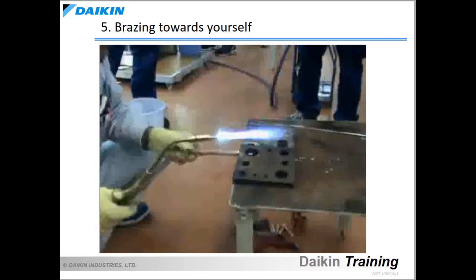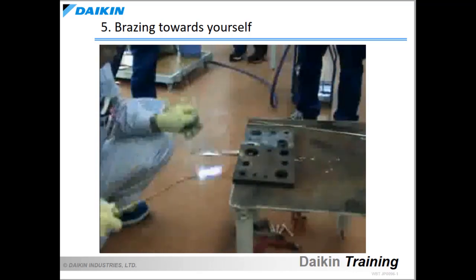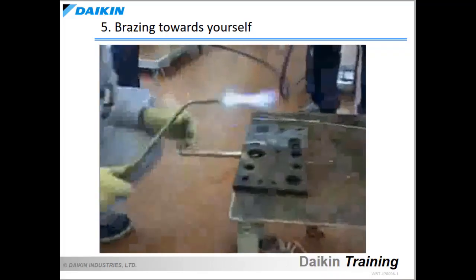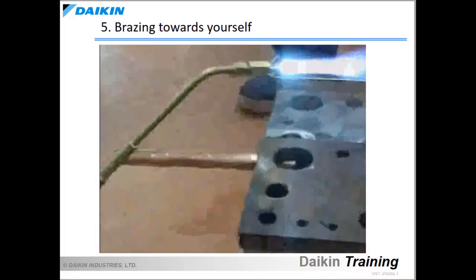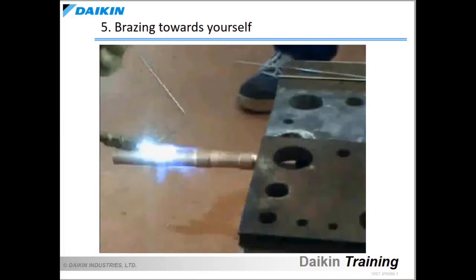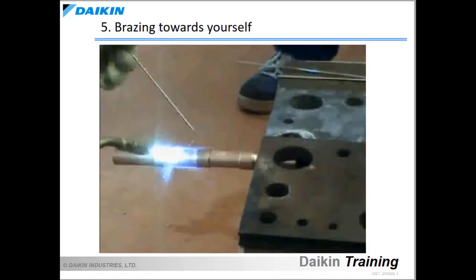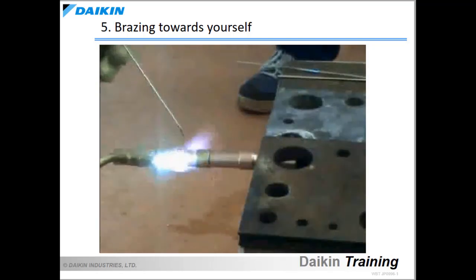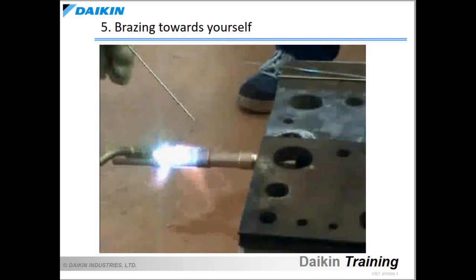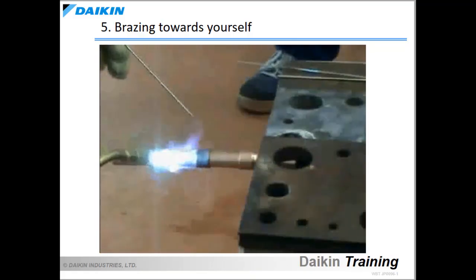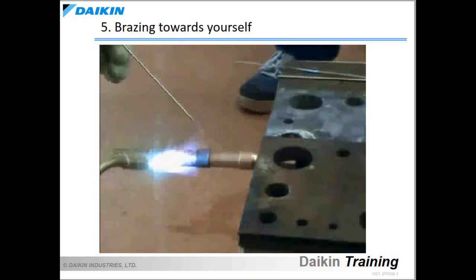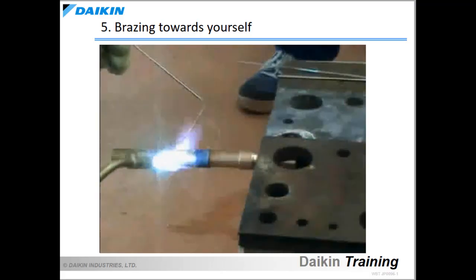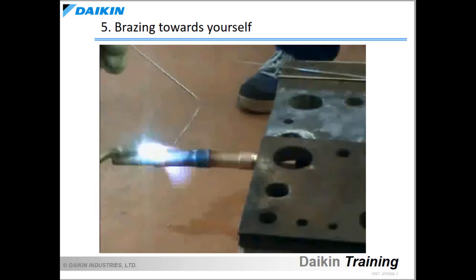Move the flame upward from the bottom to guide the brazing filler metal from the bottom to the top of the joint. Move the flame to the top of the joint and slightly away from the pipe to create the build-up in a half-molten state. Move the flame to the flare bottom to spread the brazing filler metal inside the joint from the top to the bottom. Finally, create the build-up and check the entire circumference of the brazing area.